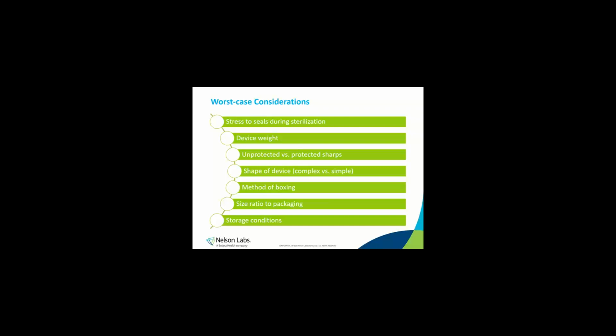This also relates to stress on the seal. Which device has the most sharp edges or protrusions that could potentially create holes in the package, either directly or through abrasion during transportation vibration? How are the devices packaged? Do some have more or less protective packaging than others? How does the device size compare to the packaging? Improperly sized packages can cause more stress to the package.